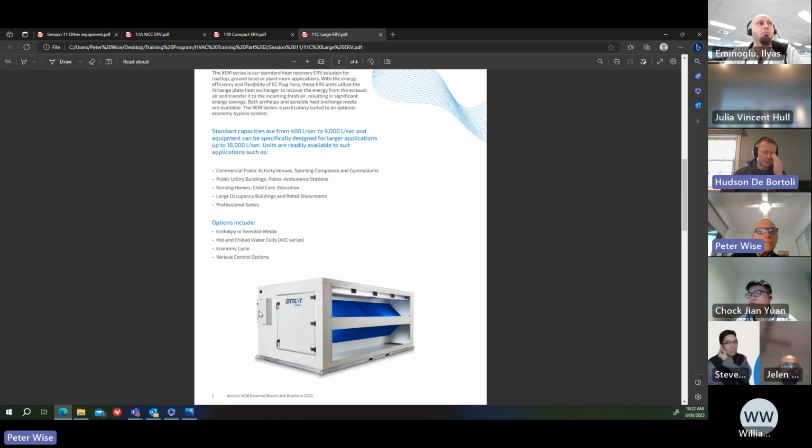Yeah, because that question did come up because we're like, if you're recovering energy from toilets, let's say, and you've got all this moist toilet bathroom air, and then you're transferring that recovering heat to drier outside air, are you going to get humidification of that outside air, even if it's a sensible only ERV? And the question is, if it's sensible only, then how do they stop that from happening? How does that not occur?